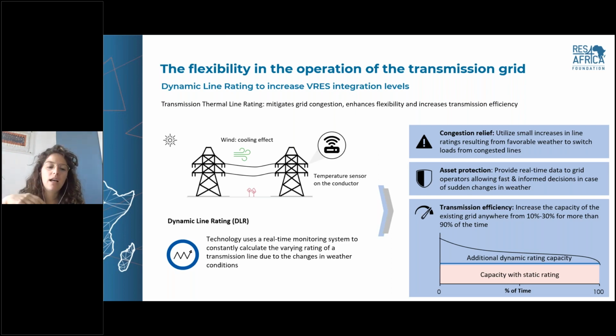With dynamic line rating, this implies putting sensors on the line, having advanced computational techniques for computing the actual capacity of the line, and also weather forecasts to understand the weather conditions. This will allow the line to flow a lot more current, which may help in moments of congestion to better dispatch the power plants. So we may dispatch more on a congested line than expected. This is also very interesting for wind turbines, which produce a lot when there is wind. When you have high wind production, you know the line is cooler thanks to the wind cooling effect, so you can exploit those lines more and flow more wind power through them. It's very interesting due to this contemporaneity with wind production.